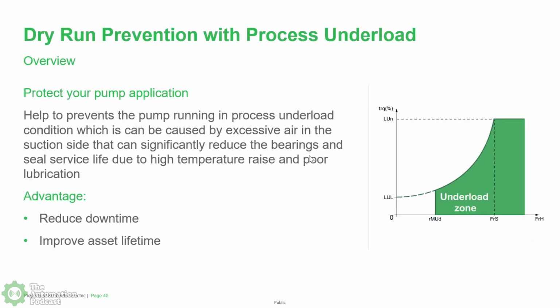Dry run prevention is also something we have in the VFD itself. So if there's a lot of air, or there's not enough water, we also prevent the pump from running to make sure that we don't damage the motor. So this will help reduce downtime and make sure that the VFD and motor are protected in those circumstances.